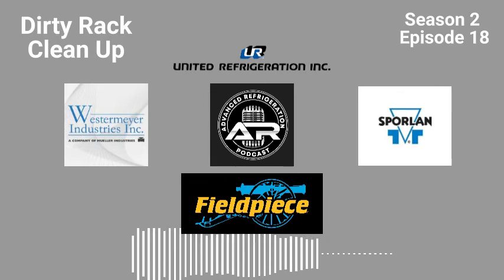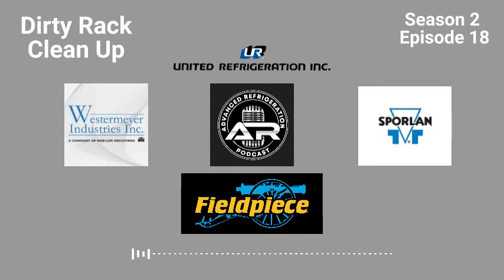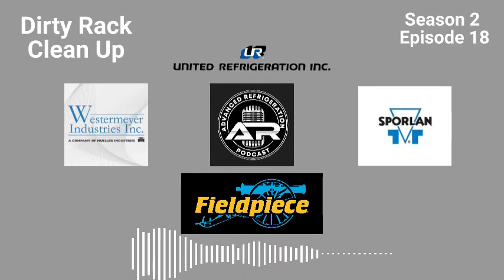Typically after startup, they're supposed to yank them out. It depends on the customer. All the customers I've seen the spec for, you'd be surprised, there's a lot of customers who don't want them out, which makes sense. They're there for a reason. I usually, depending on what it is, will change them after the first week. I'll change it on startup, change all the dryers, get the suction filters in. And if the suction filter is clean when I pull it, I usually just leave it out.